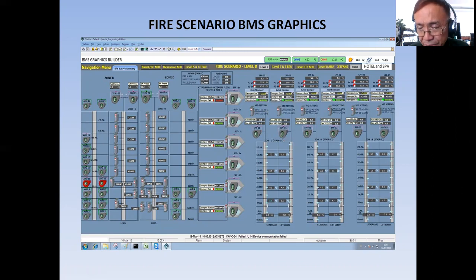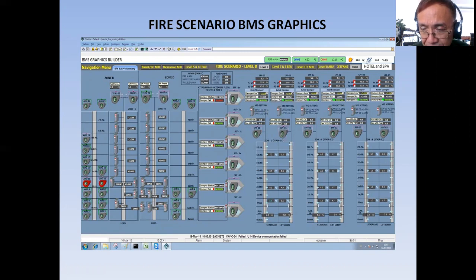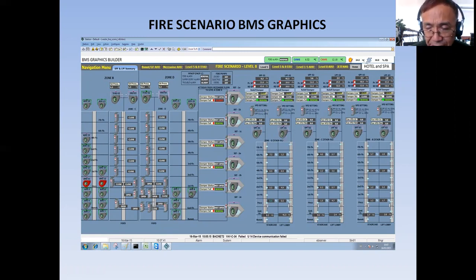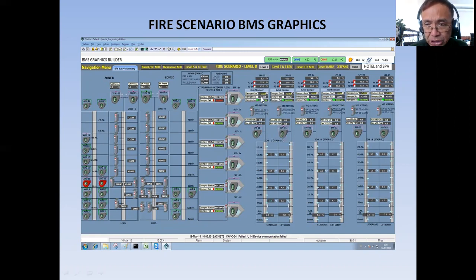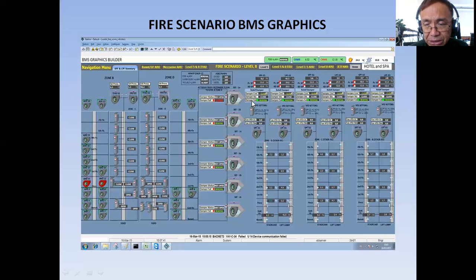There is also a damper fail indication. Damper fail is when the BMS gives a command to open and the damper did not open within a certain time delay — then BMS will raise an alarm to check this damper, because BMS gave the command to open but it did not respond.